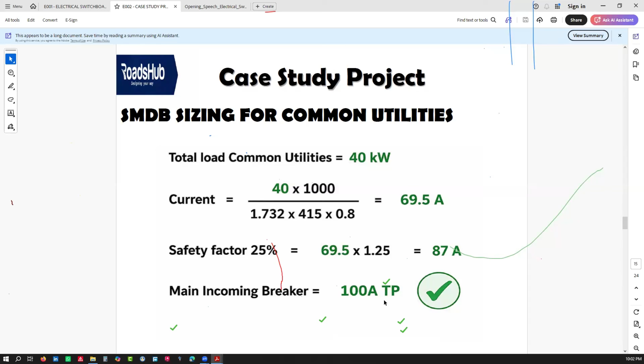So you have your SMDB, you have your main DB. So how many SMDBs do you have? You have 6 plus the commons. You see now for common services, we talked of 100. Actually, the actual common services value we got was 100. If I'm not wrong, we had 100 TP here. So this 100 TP, when it comes to the main DB where we are getting the power, we put a 125 because the kA value will shoot a little, because now on the main DB, the systems are carrying all the weight of all the DBs for 2 BHKs and 3 BHKs.